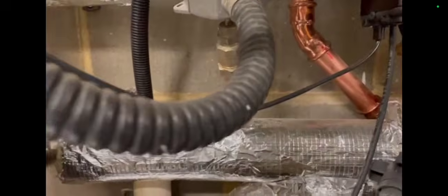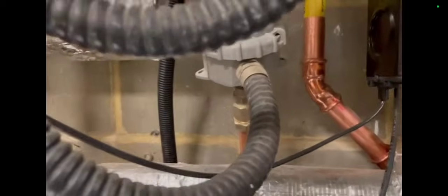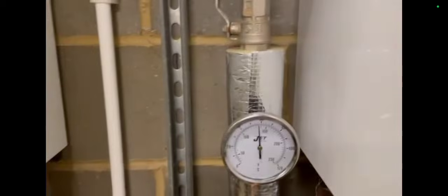And then I proceeded to start taking out the probes. So I had the probes out and I gave them a clean. Ignition and detection were both cleaned. Then I moved on to cleaning out the Magna Clean because there were flow and return issues. The temperature was rising far too quickly. I thought I'd give the Magna Clean a wash out and also to just see the system's condition.